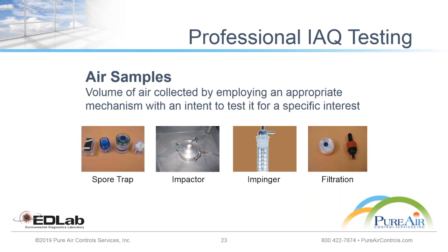On the other hand, they can collect the air sample by using various kinds of air sampler, and there is a test methodology called spore trap analysis, in which they collect the specimen, which is tested in the laboratory using either microscopy or culture method, by which it is determined whether any biological or abiological substance is there which might be problematic.